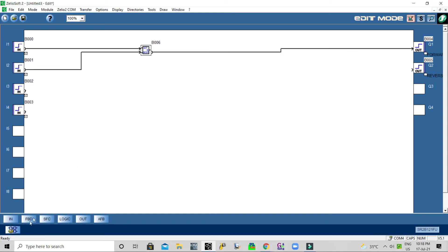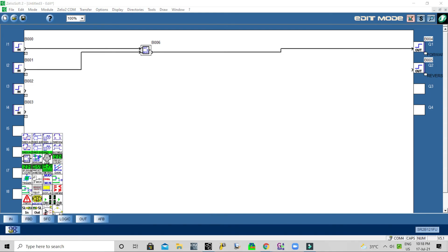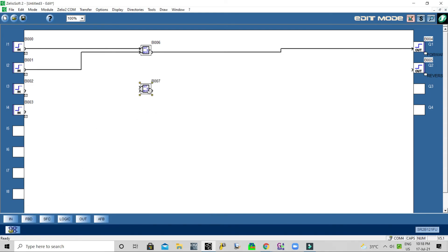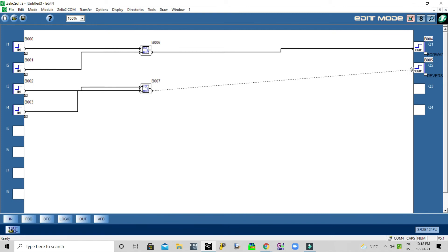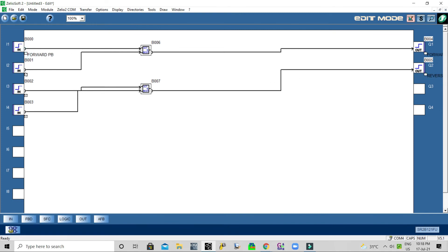Then I take one more RS switch block and connect the reverse push button to set, the reverse limit switch to reset, and the output to the reverse output contacts.